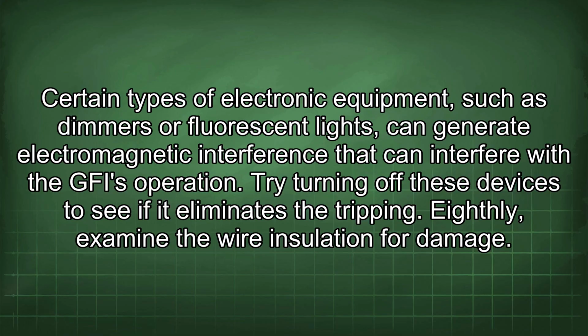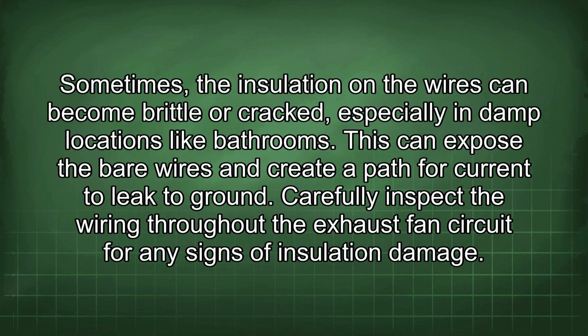Eighthly, examine the wire insulation for damage. Sometimes, the insulation on the wires can become brittle or cracked, especially in damp locations like bathrooms. This can expose the bare wires and create a path for current to leak to ground. Carefully inspect the wiring throughout the exhaust fan circuit for any signs of insulation damage.